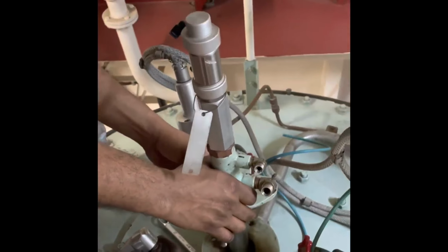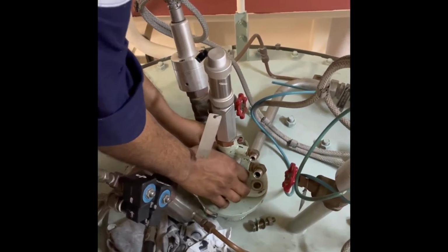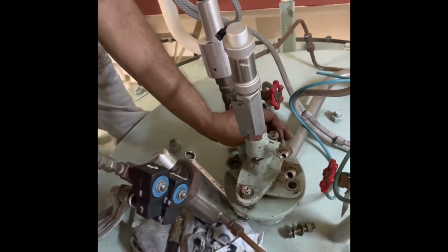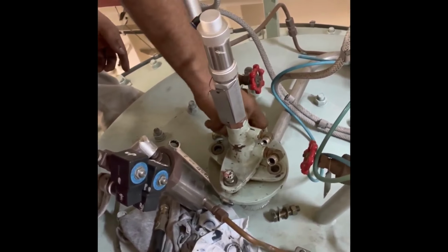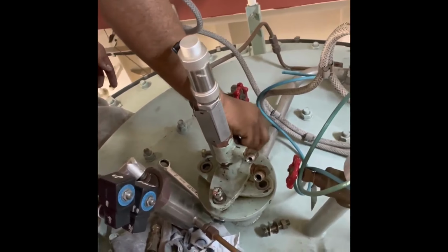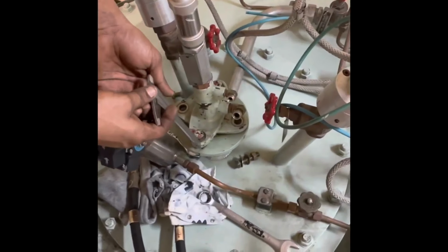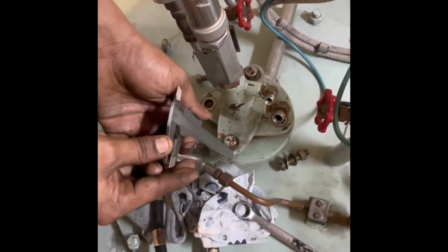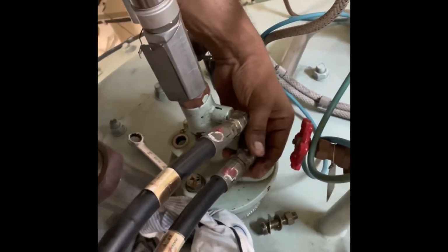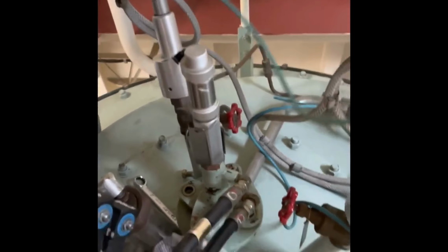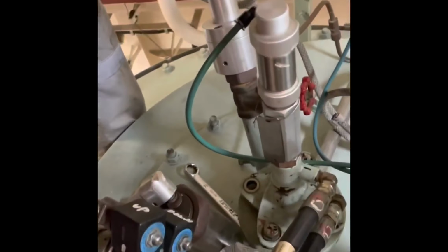Then place the oil burner on the burner top, and check and adjust the burner height. I would say the average value may be 55 to 59 mm, and then tighten the burner height adjusting bolts. In my case the height was around 58 to 59 mm. Then tighten the two stuffing box bolts, and then connect the oil inlet and return pipelines and connect the air lines to the air cylinder.